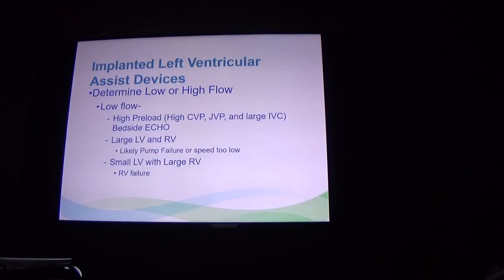Now if you have a low flow issue but you have high preload, so your CVP is through the roof on your monitor and your IVC is super plump on your bedside echo, if you have a large LV and a large RV, basically the heart looks really big on both sides, this is likely a pump failure or the speed's too low. And most likely, if you don't hear a hum or your power's real high on the device, because the motor's trying to work but it's just not able to spin, that's really bad. You need to consider anti-thrombotic agents to help with that. Or if you have a very small LV and a large RV, you've got to consider right ventricular failure. These are all things you're going to want to tell the LVAD coordinator when someone actually does get them on the line.